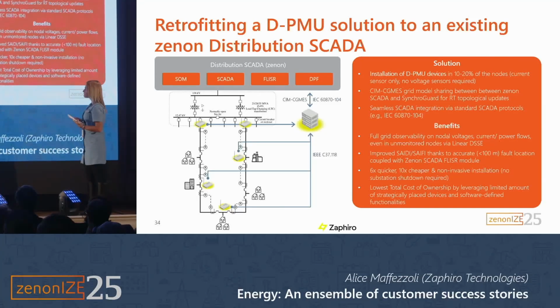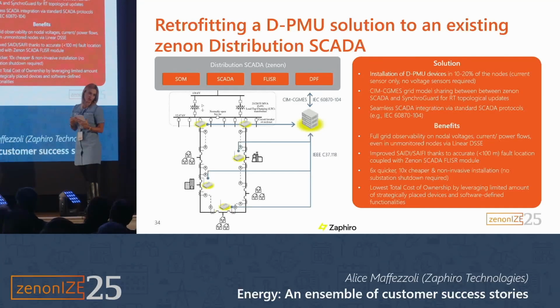Integrating with the SCADA can be done at different levels, so we can either send all the information, so real-time visibility, which is generally not totally well accepted because it's too much information and too much data. What we see is the biggest interest is to have some selected alarms, either on only outages or also some power quality events that are particularly interesting. And then proactively, the control room operator can go and open our dashboard to check in detail what happened. The other important thing of an integration with a SCADA system is that it allows us to receive automatic topology updates, which is something that is needed for our platform to work. So it's really a bi-directional communication: on our end to send alarms to the SCADA system and also to receive topology updates.